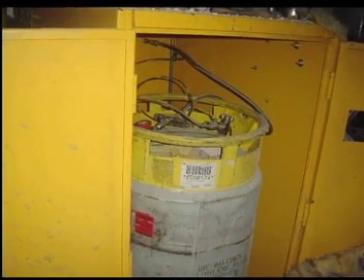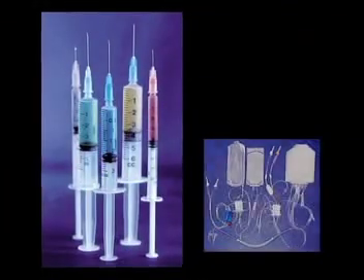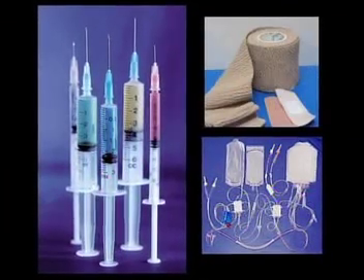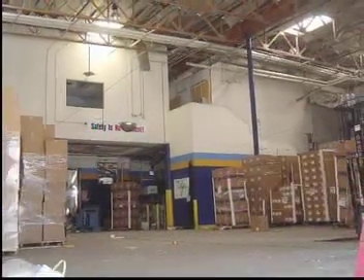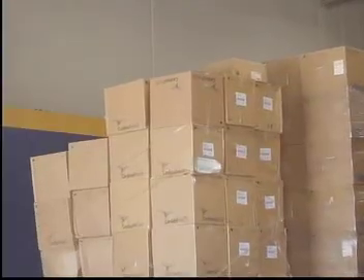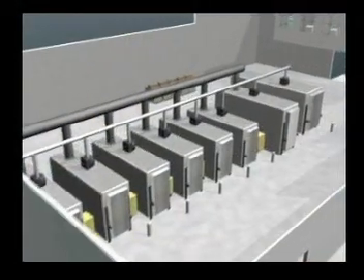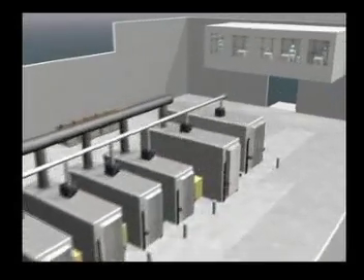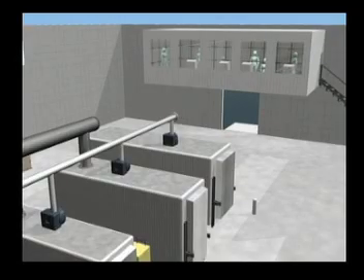Sterigenics International uses ethylene oxide to sterilize medical products such as syringes, catheters, and bandages and then ships them to medical suppliers. Products arrive at the plant pre-packaged and stacked on pallets ready to be sterilized in large steel chambers. The plant contains eight sterilization chambers, operated and monitored by personnel using a computer system in the control room.